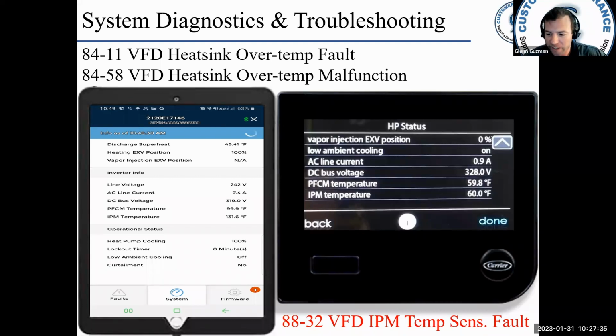8832 is VFD IPM temperature sensor fault. Basically, there is a sensor in the VFD. It's failed. The only way to fix that one is to replace the VFD.